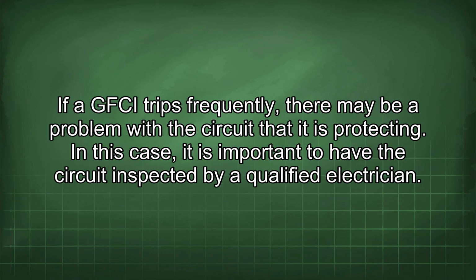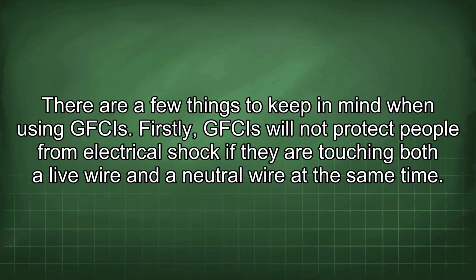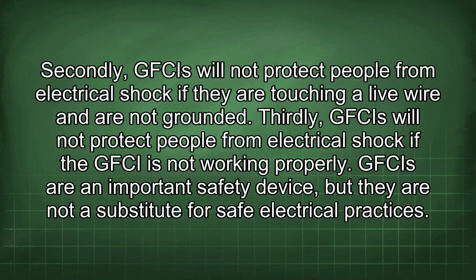If a GFCI trips frequently, there may be a problem with the circuit that it is protecting. In this case, it is important to have the circuit inspected by a qualified electrician. There are a few things to keep in mind when using GFCIs. Firstly, GFCIs will not protect people from electrical shock if they are touching both a live wire and a neutral wire at the same time. Secondly, GFCIs will not protect people from electrical shock if they are touching a live wire and are not grounded. Thirdly, GFCIs will not protect people from electrical shock if the GFCI is not working properly.